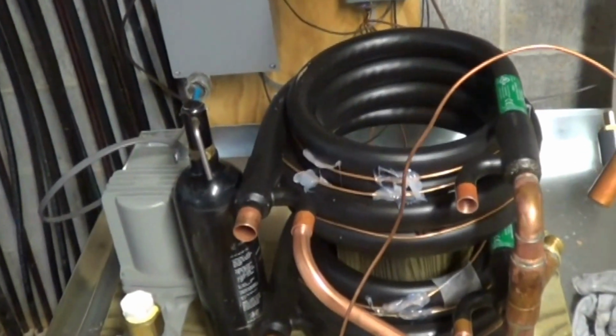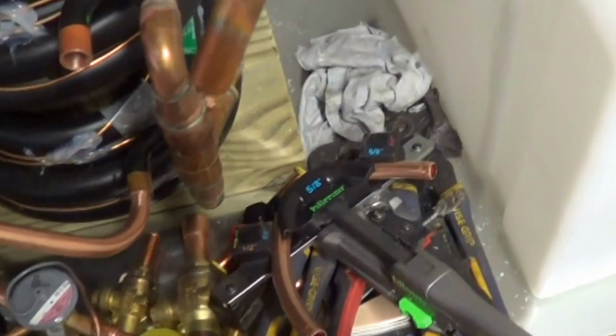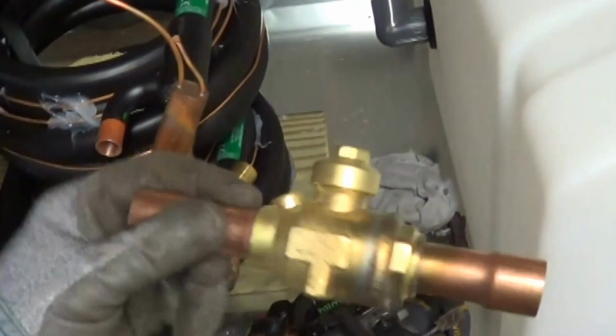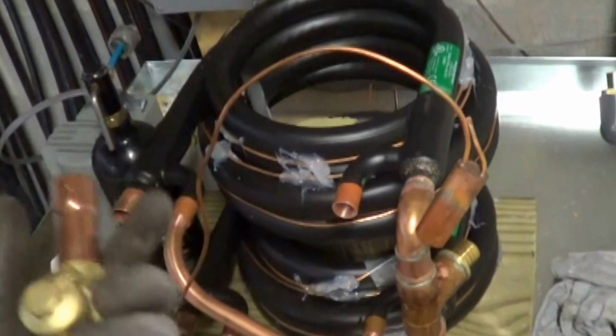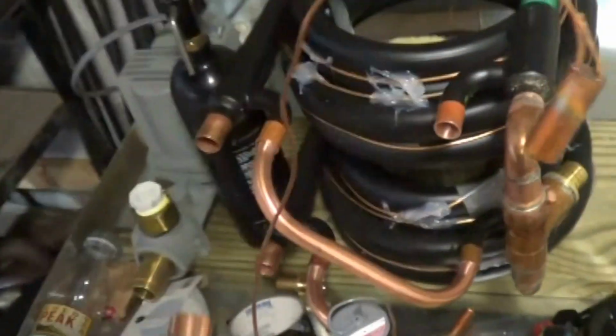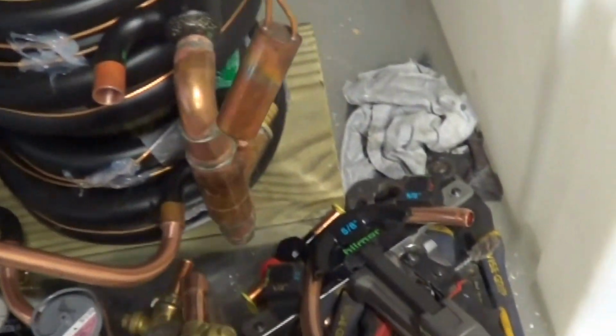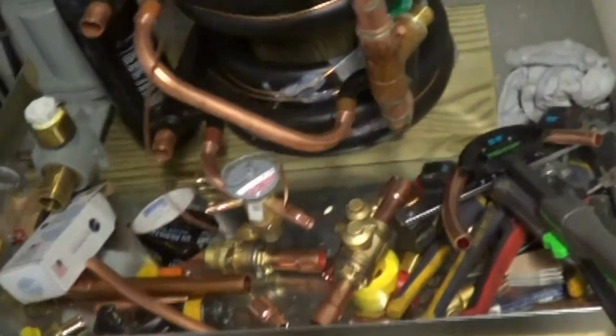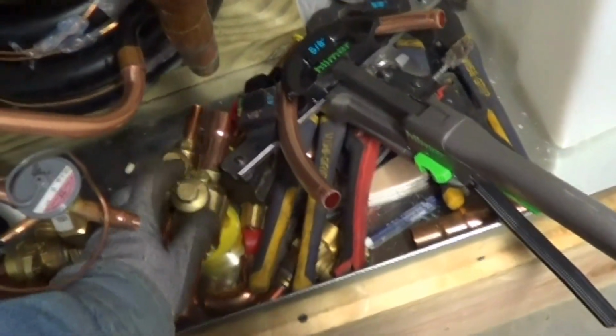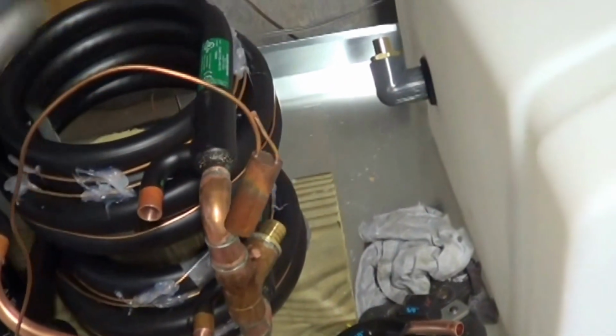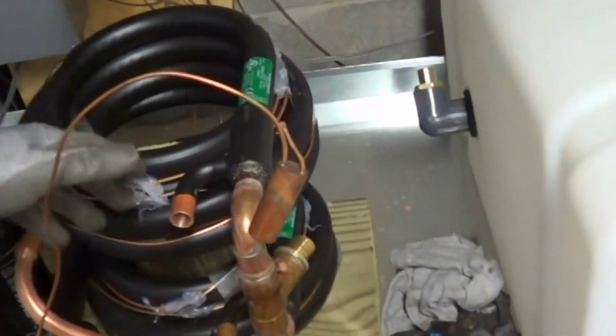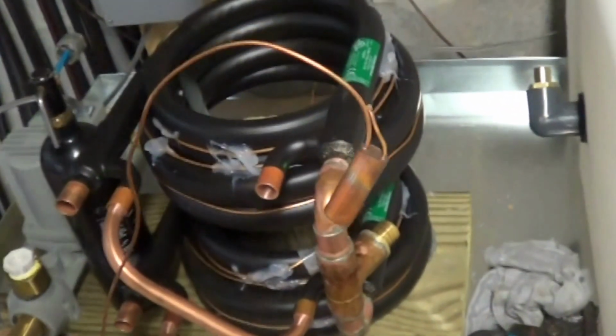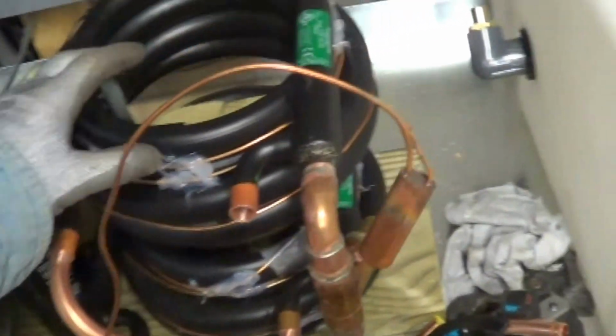I'm putting a couple safeties here because the customer is actually going to be doing a switchover by pumping down, isolating either the heat pump or isolating the air handler. And so they can use the same condenser unit in the summertime versus the winter. And with 4 isolation valves, I'll show you those, I have to install those. But basically it's just you pumping it down, valve off, and then you can run the other circuit. But you have to do some safeties to make it foolproof.